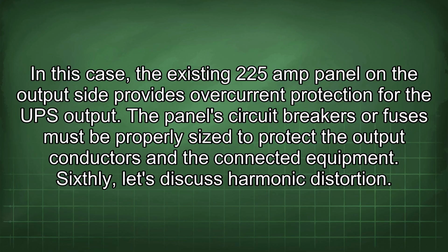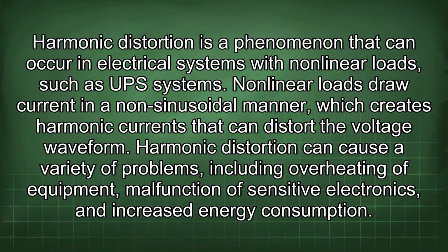Sixthly, let's discuss harmonic distortion. Harmonic distortion is a phenomenon that can occur in electrical systems with nonlinear loads, such as UPS systems. Nonlinear loads draw current in a non-sinusoidal manner, which creates harmonic currents that can distort the voltage waveform. Harmonic distortion can cause a variety of problems, including overheating of equipment, malfunction of sensitive electronics, and increased energy consumption.